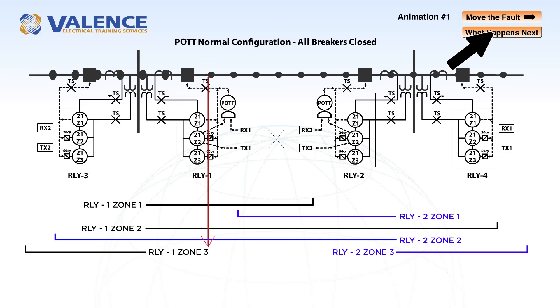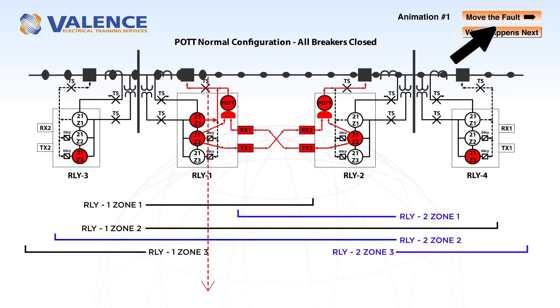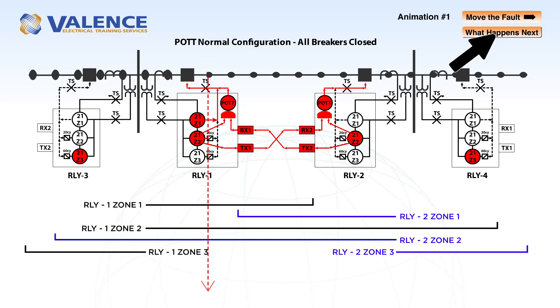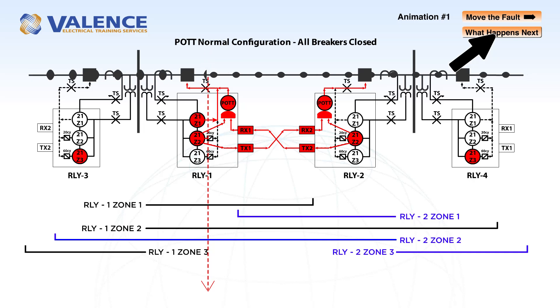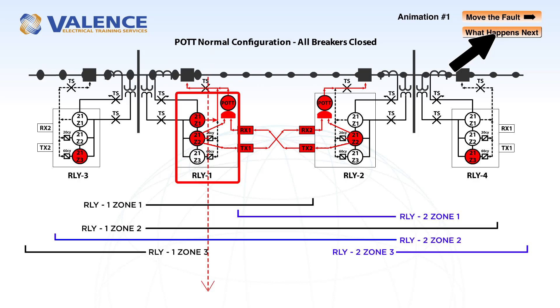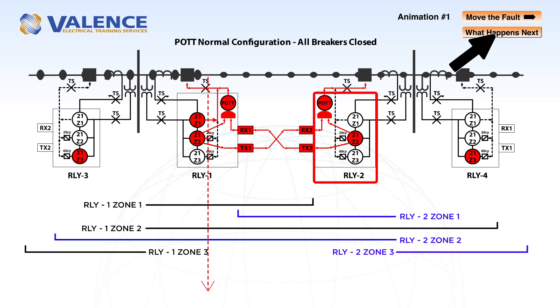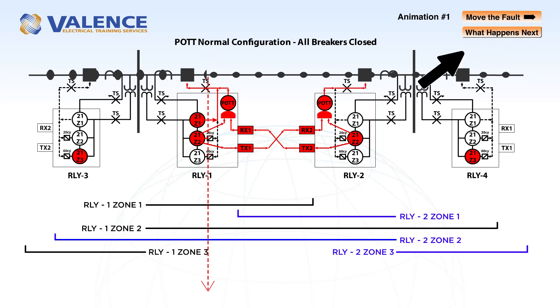If the fault occurs next to relay 1, the relays will detect the fault as if there was no communication enabled because those settings haven't changed. Relay 1 detects a zone 1 and zone 2 fault, and relay 2 detects a zone 2 fault.